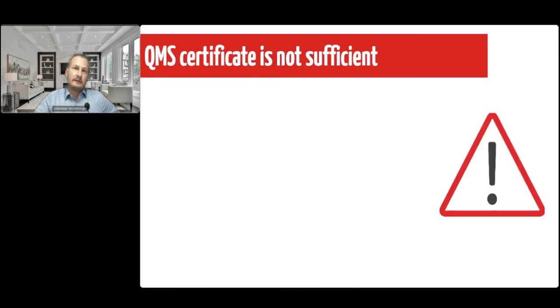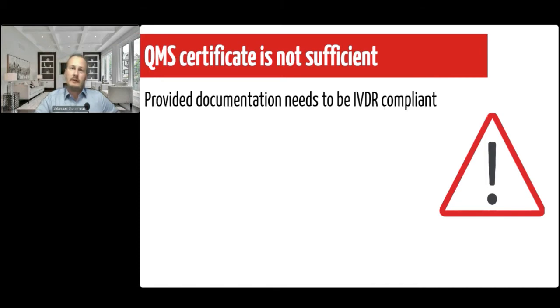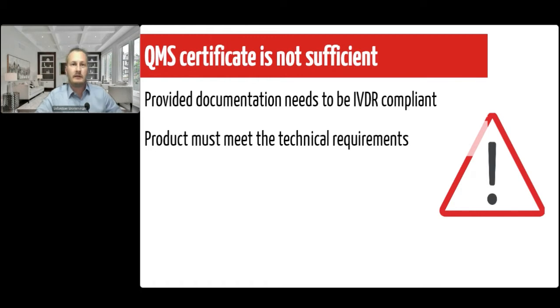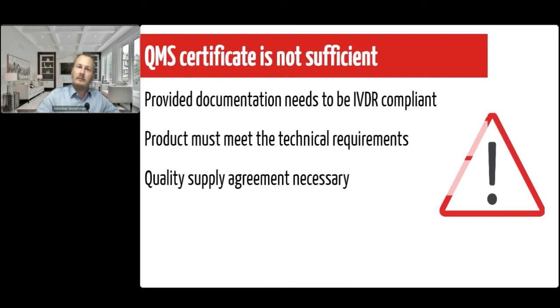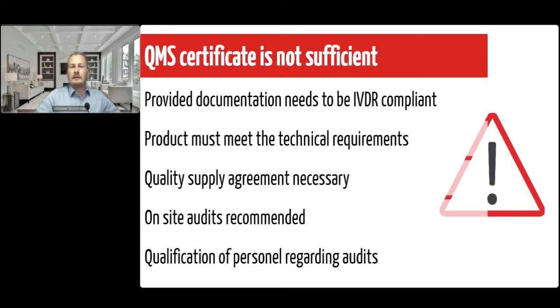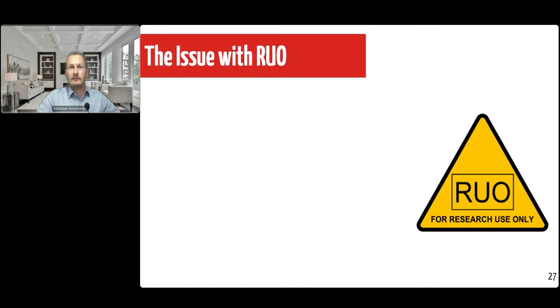So what I want to tell you is a quality management system certificate is not sufficient. The documentation needs to be IVDR compliant. The product must meet the technical requirements, and quality supply agreements are necessary with the suppliers. And on-site audits are recommended. And the qualification of the personnel regarding audits must be available. So all of these must be provided by the laboratories if they take over responsibility for manufacturing.